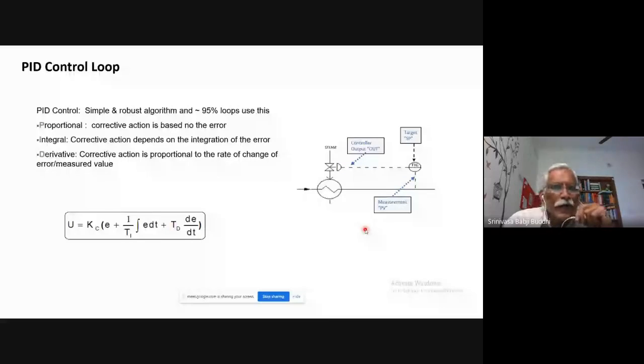In most industries, almost 95% of the loops use this PID control algorithm, because it is very simple and robust. There is nothing much to go wrong with using it, and it is simple to implement and tune. When I say proportional, integral and derivative, we are talking about three contributions in this control algorithm. Proportional: the corrective action is based on the error. Integral is based on the cumulative error present in the control loop. And derivative is based on the slope, or the rate of change, of the process value or error. Based on the slope, you take the corrective action.